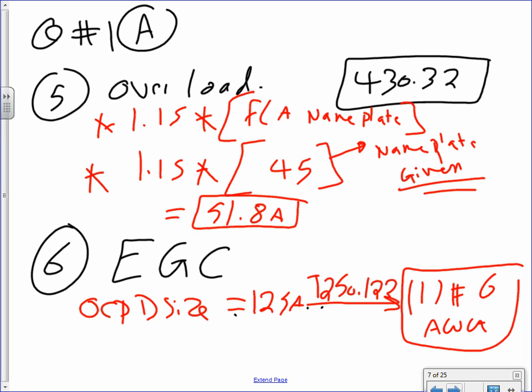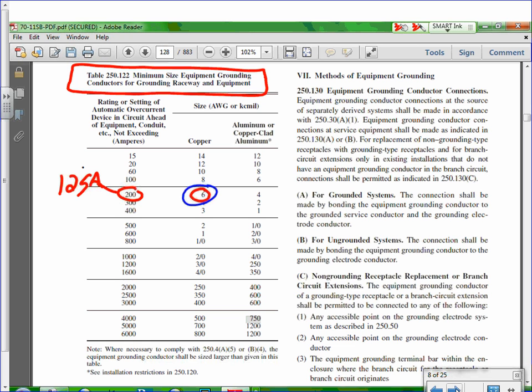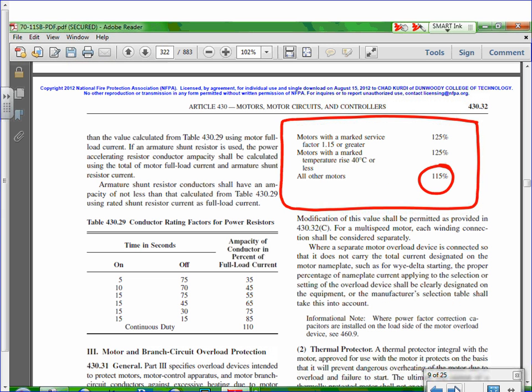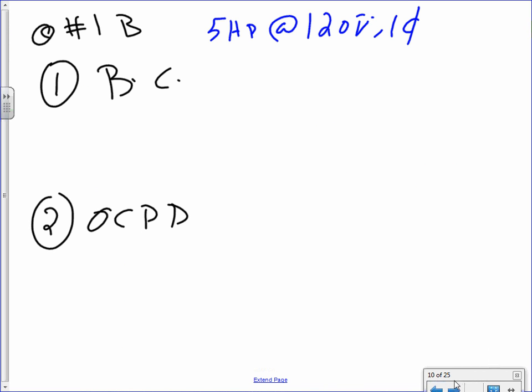Any comments, any questions? Now, if you missed everything I've done, there's another chance to do one more. You can see I'm going over these examples. Here's Table 250.122, you go to number 6. I want to emphasize that these are PDFs and on the network too, for your review. Here's the 1.15 for the overload. Now let's go to the second motor. We're going to repeat the same 6 steps for the second motor. Hopefully it will sink in, and I'm sure it will. So for a 5 horsepower motor, 120, I want to emphasize this is a 120.